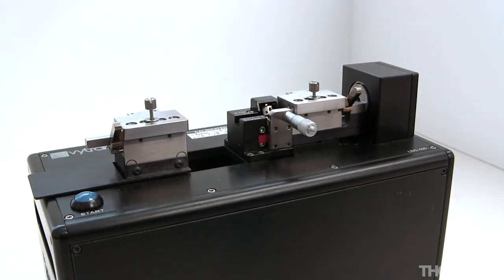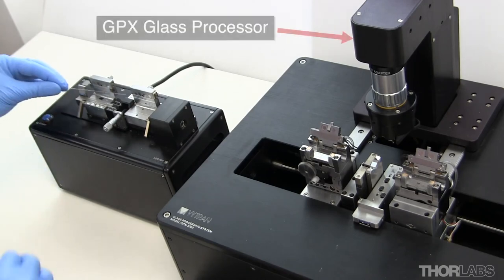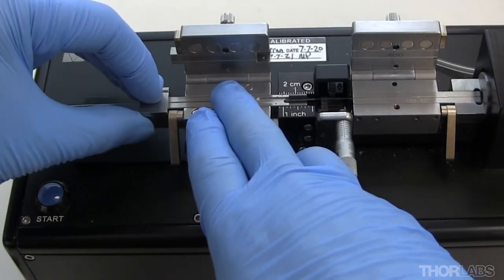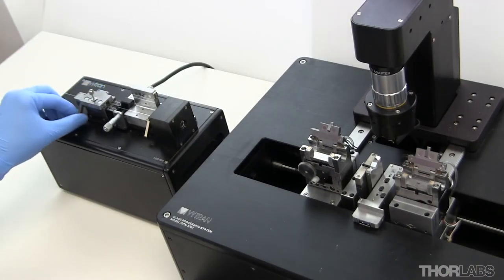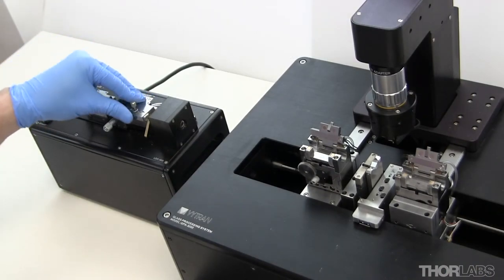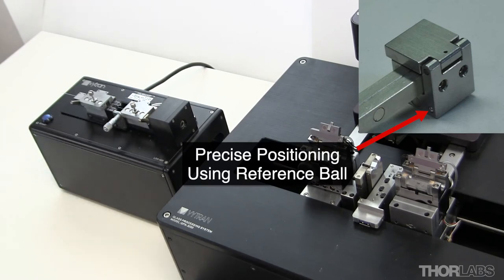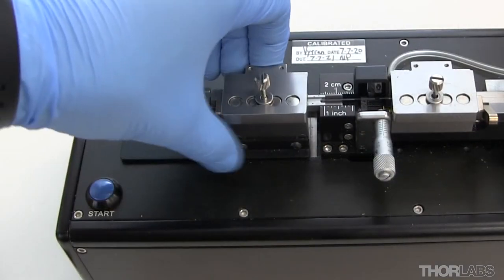The cleaver inserts are now fully installed and the cleaver should be ready to use. If you are using a cleaver in conjunction with a Thorlabs Vytran glass processor or LFS splicer, it is beneficial to use a transfer insert. The transfer insert assembly maintains accurate fibre position registration as the fibre is moved from the cleaver to the glass processor or LFS splicer.